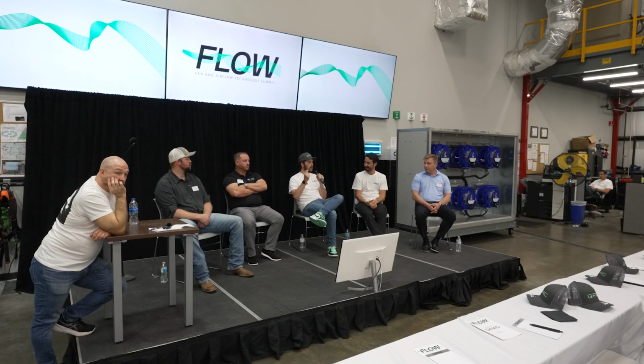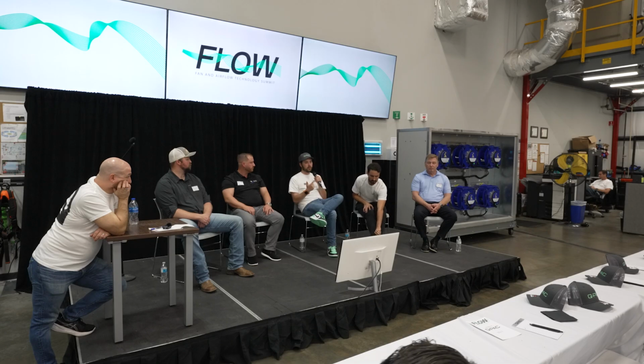Yeah, that's a great question. Whenever I hear the word harmonics, there are two sides of the coin I worry about. One, we don't want to be adding any additional harmonics to the system, and two, we want to be resilient to any harmonics already on the grid. A lot of these buildings already have some level of existing harmonics, so we need to be robust enough to maintain airflow in these existing environments, and we need to make sure we're not contributing or making the problem worse.